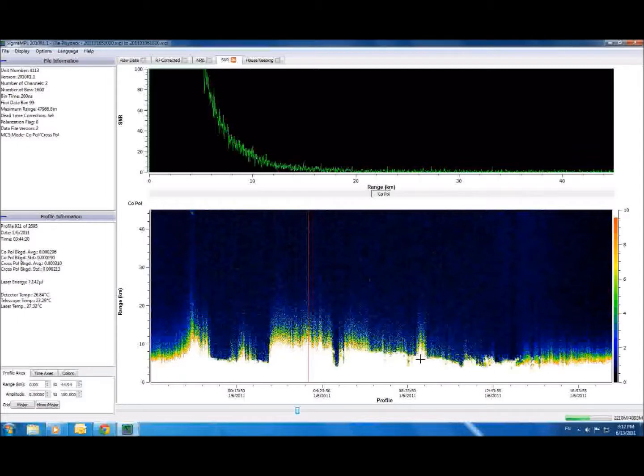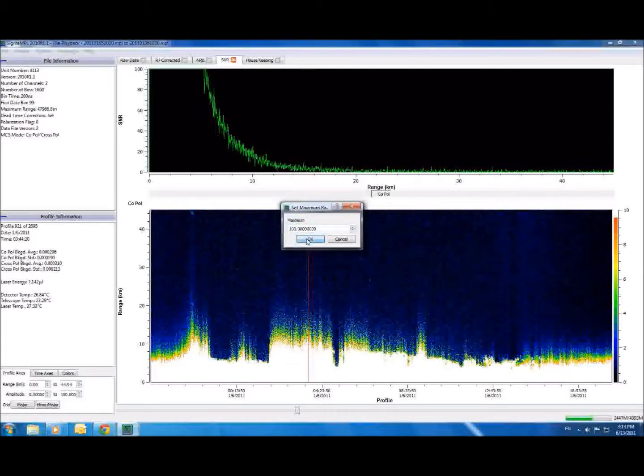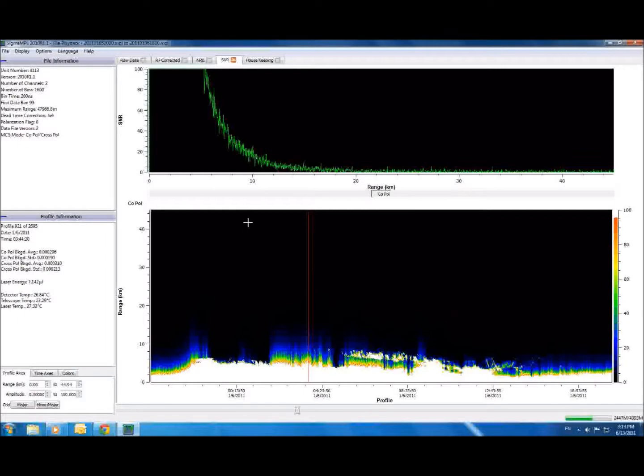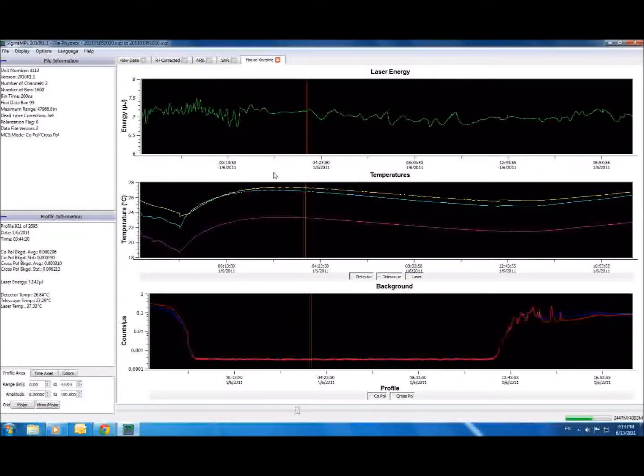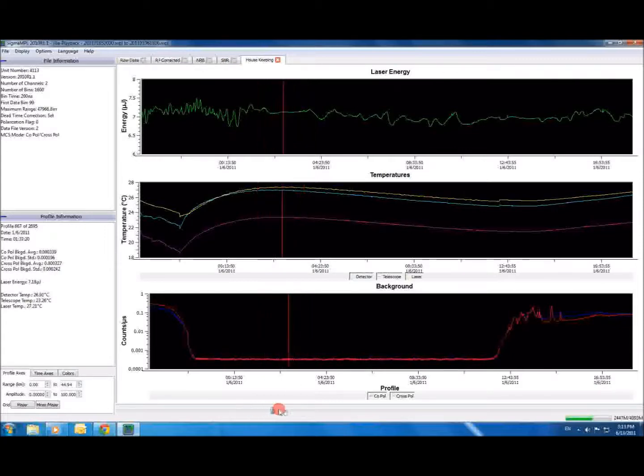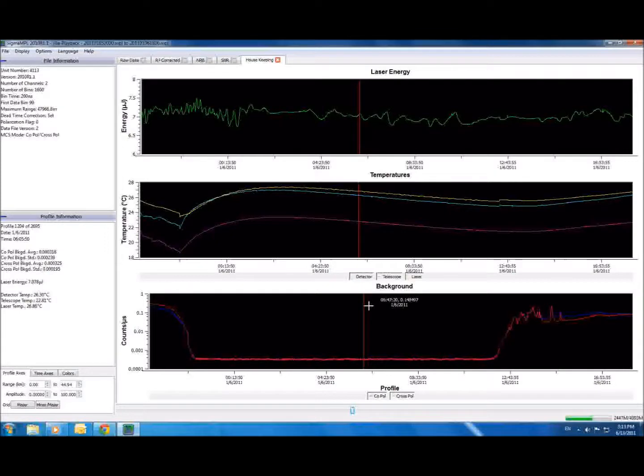Other typical values used by researchers are 1 and 100. The last tab we will mention in this video is the housekeeping tab. Here, we can watch how the laser energy, temperatures, and background counts change over time. Notice how the sunset and sunrise are clearly visible in the background graph. Remember, Sigma MPL already compensates for both background and laser energy in its data processing, so there is no need to adjust your interpretation of the data based on anything you see here.